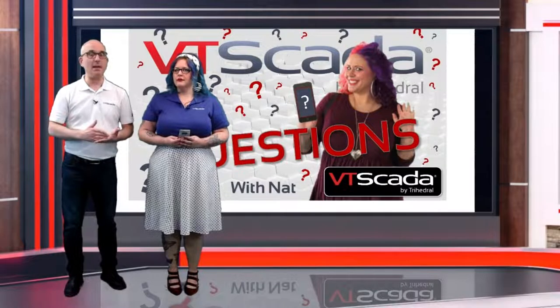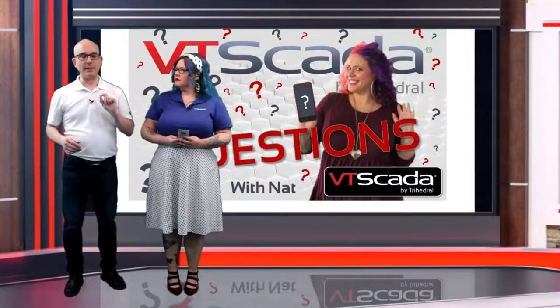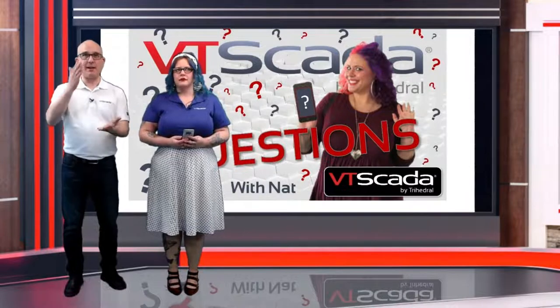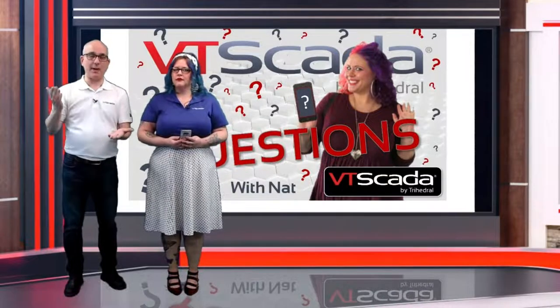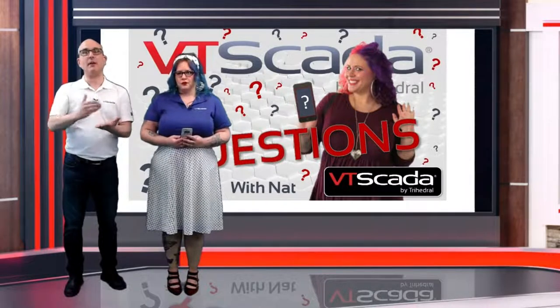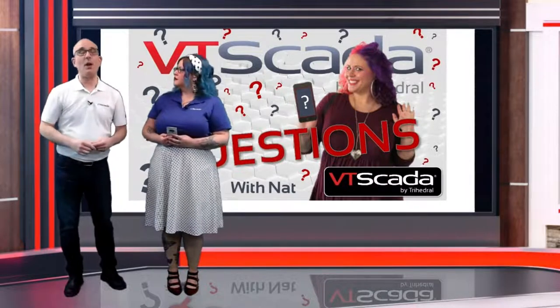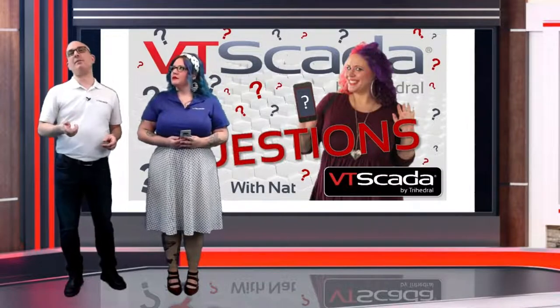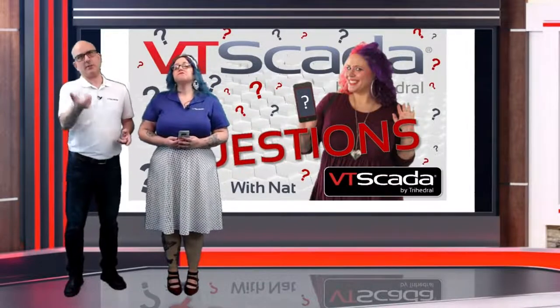So if there is a problem, that's usually because of one of two things. One is that your polling rate is higher than you need it to be. That's the rate at which your HMI or your historian is actually recording values that come in from your sensors or your various IO. So I would go in and look at that. Odds are it's turned way up because somebody by default decided more data, good.